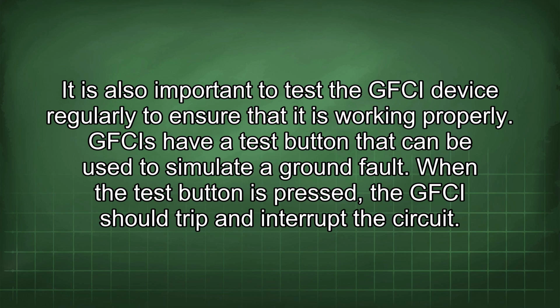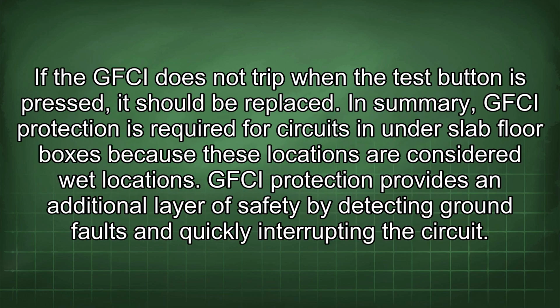It is also important to test the GFCI device regularly to ensure that it is working properly. GFCIs have a test button that can be used to simulate a ground fault. When the test button is pressed, the GFCI should trip and interrupt the circuit. If the GFCI does not trip when the test button is pressed, it should be replaced.